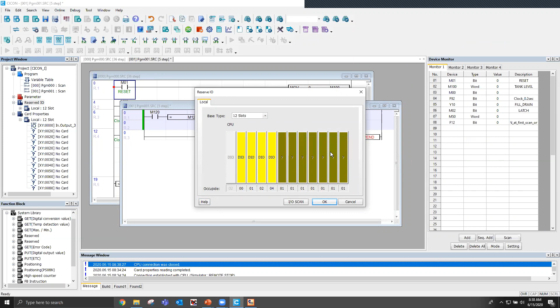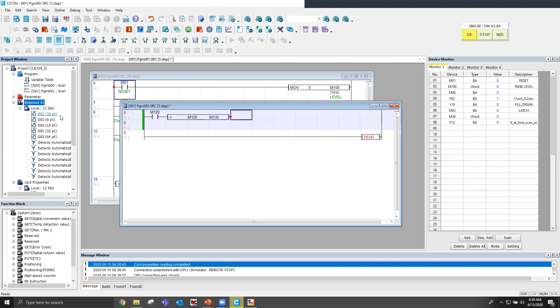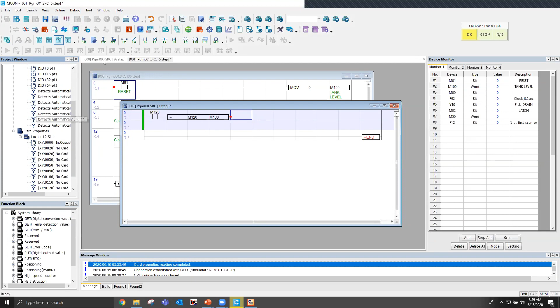The chassis automatically detects what modules you're using physically, which is pretty cool. It allocates the data properly, and as we can see, the first module in line is the CPU, which is a 32-point module, so it's allocated 2 words. When I say 2 words, it looks like it's only jumping up 20, but that's actually 2 words - 1 and then 2 - because this is in hexadecimal. If I do 0 points, like a dummy module, then we'd just allocate 0 data memory to that.